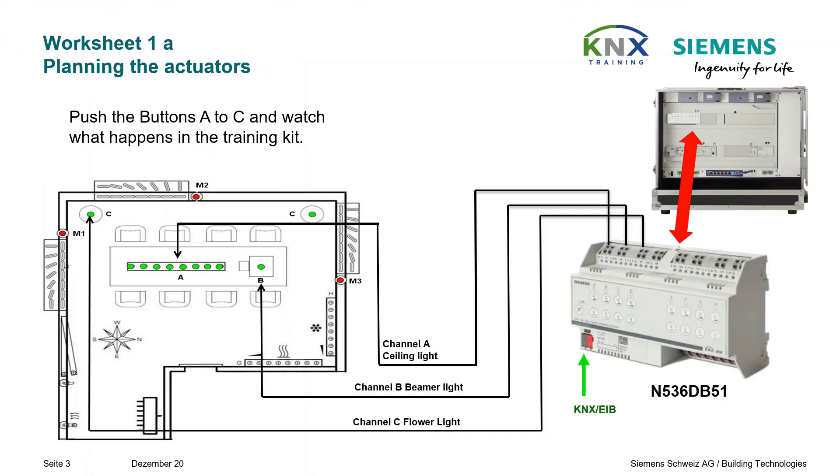In the Gamma Training Kit version 5.1 we have an 8-way switching dimming actuator, Siemens short form N536DB51, whose channels A, B, and C control the lighting circuits in the conference room. This actuator has a front side control panel for manual overrides, so it can be tested immediately after installation, wiring, and switching on line voltage, if all circuits are correctly wired and work as expected.